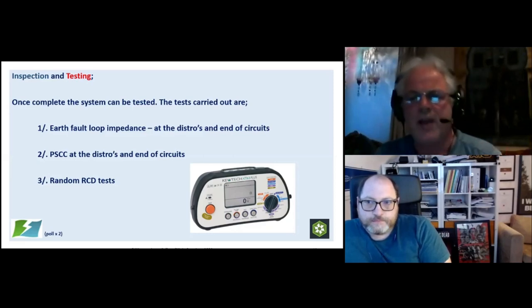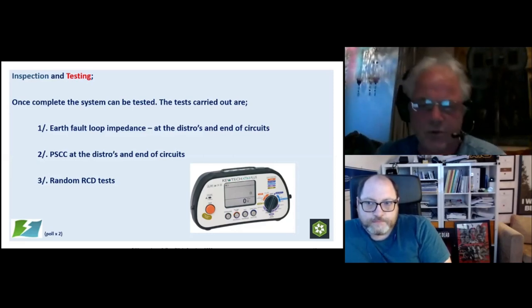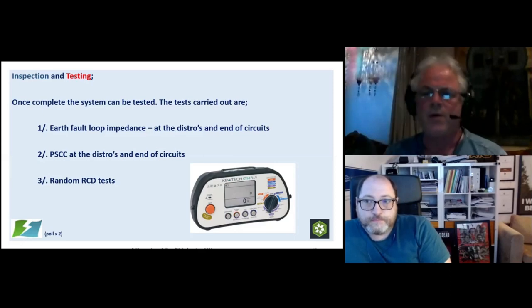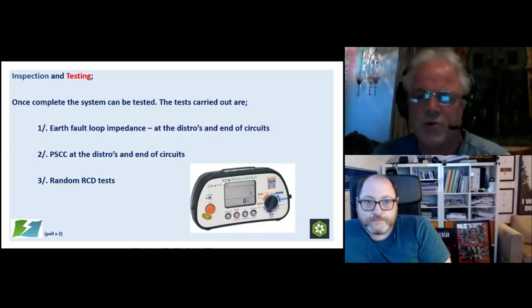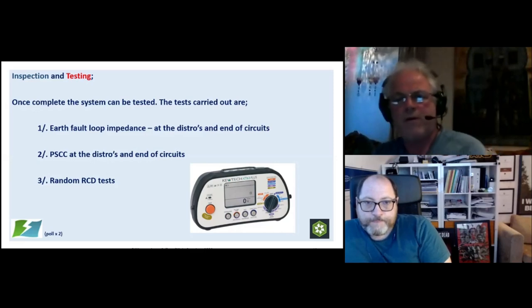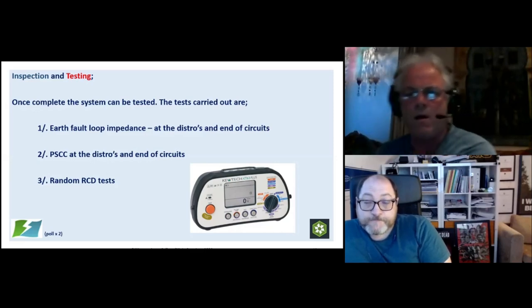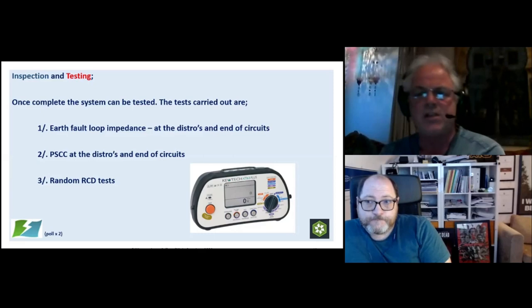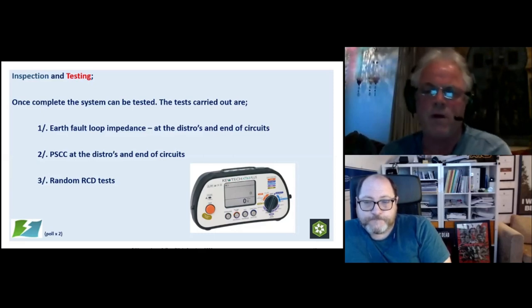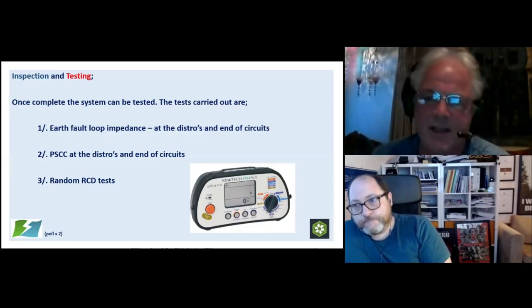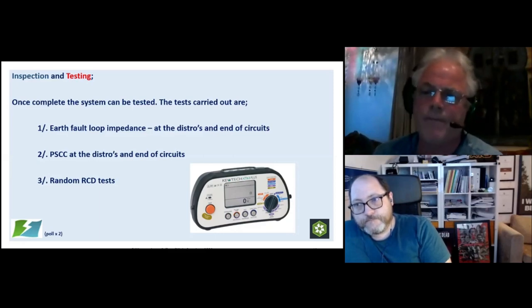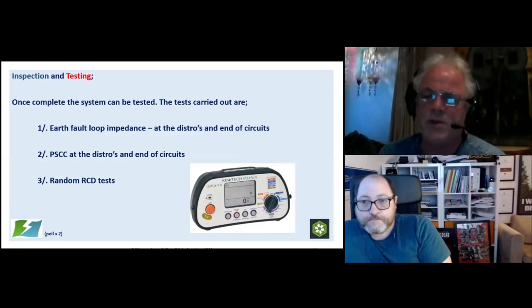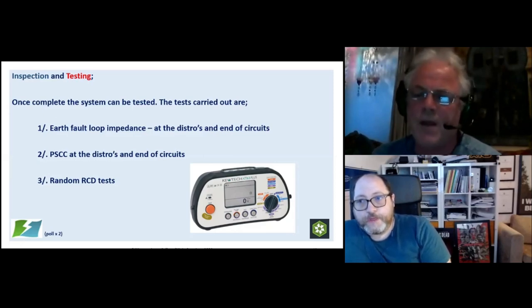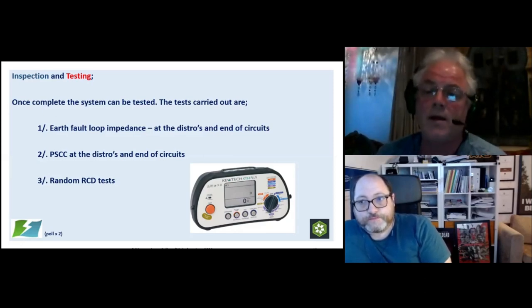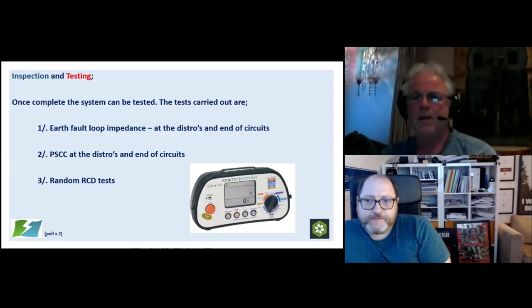Short circuit, RCDs don't work on short circuit. You may as well use a chocolate teapot. The RCDs don't work on short circuit. So if we've got a very long circuit, we may have a high impedance, which gives us a lower fault current, but the fault current might be high enough to set fire to the cable, but not high enough to take out the type C breaker. Remember that most temporary distros come with type C breakers. Some even come with a type D breaker. And you experienced this a couple of years ago, didn't you?